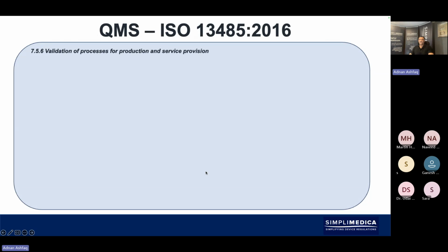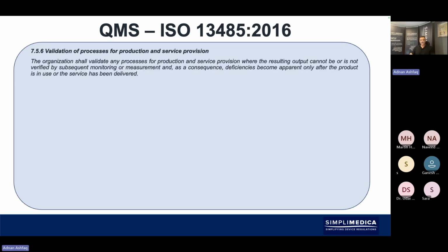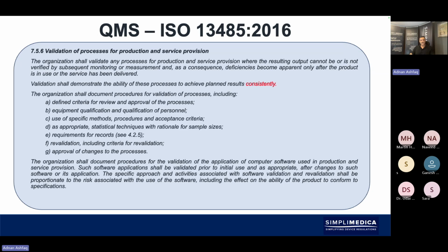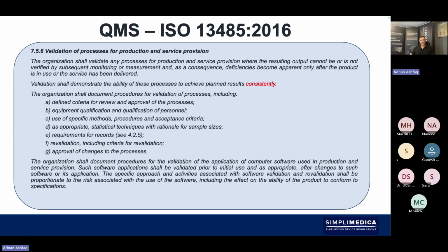So in terms of putting this into context, I'm going to give you some definitions and background to validation. So ISO 13485 contextualizes validation with the following. 7.5.6 is the specific clause which looks at the requirement for validation. It sits under the production clause 7.5, which then requires the validation of processes for production and service provision, where it states that the organization shall validate any processes for production and service provision where the resulting output cannot be or is not verified by subsequent monitoring or measurement.